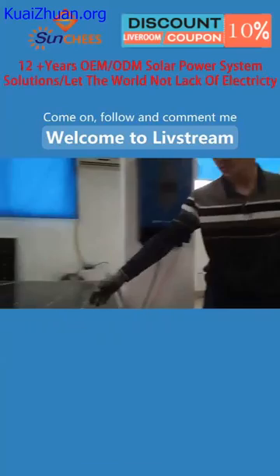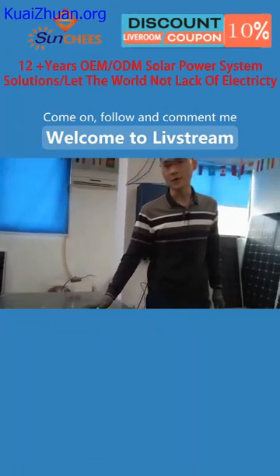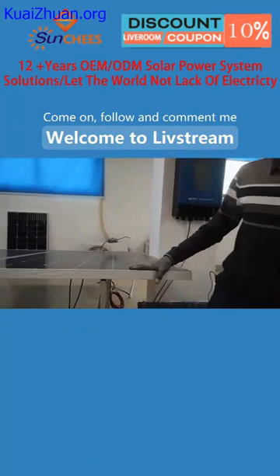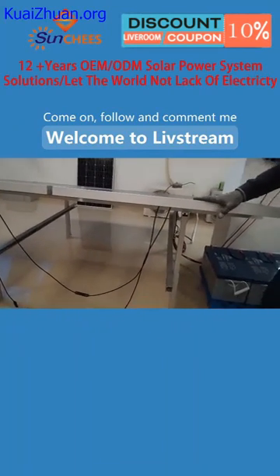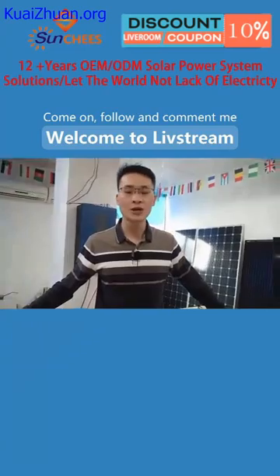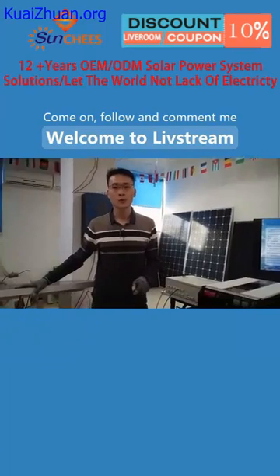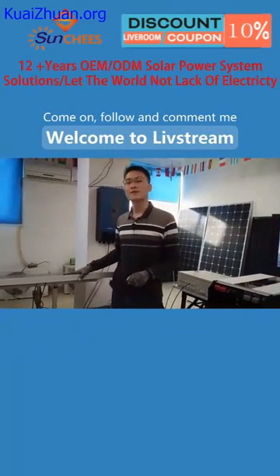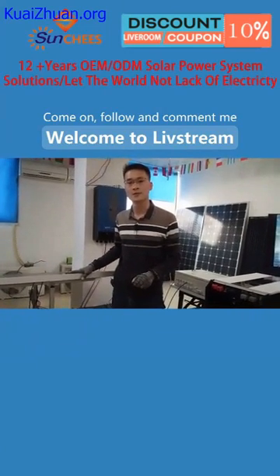This is solar panels. This solar panel is 380 watt, one piece is 380 watt. The maximum power voltage, working voltage, will be around 36 volt. For our 6 kilowatt hybrid inverter, the MPPT tracking voltage range will be between 72 to 150 volt. So if you are using 350 watt solar panels, then at least you need 2 pieces of solar panels in series connection.